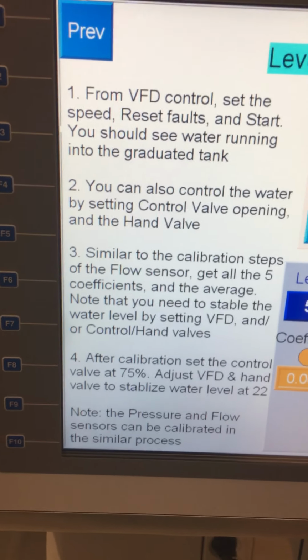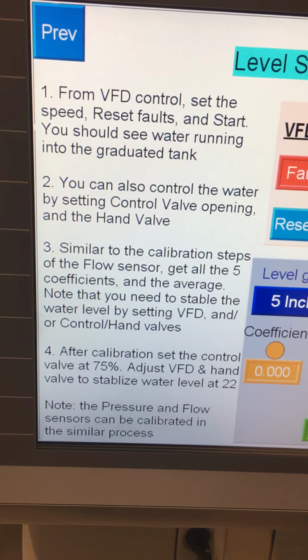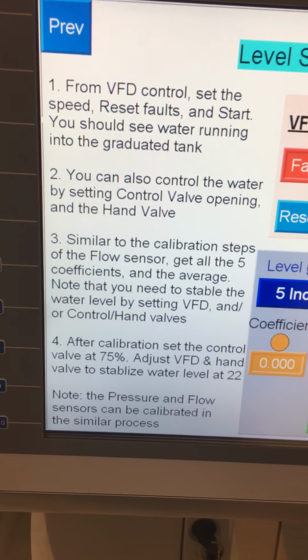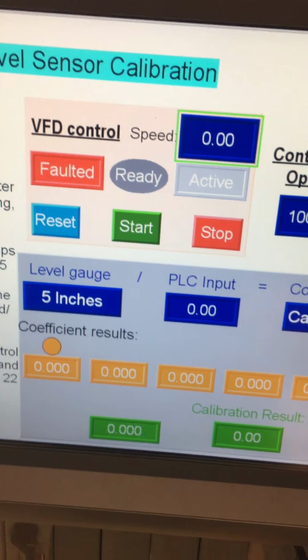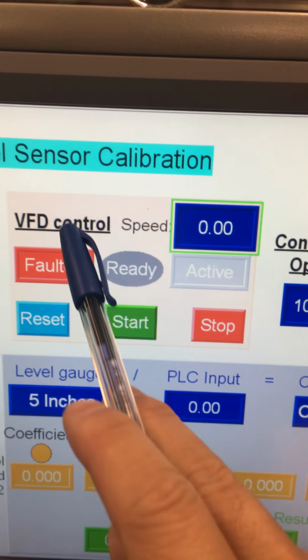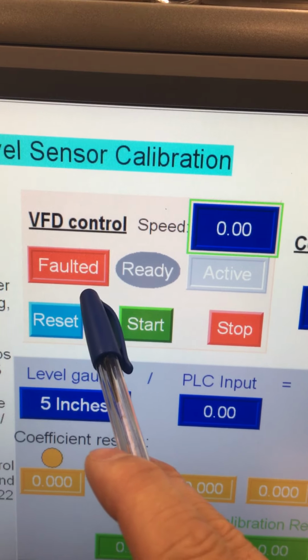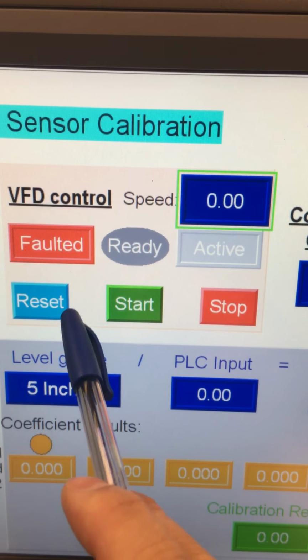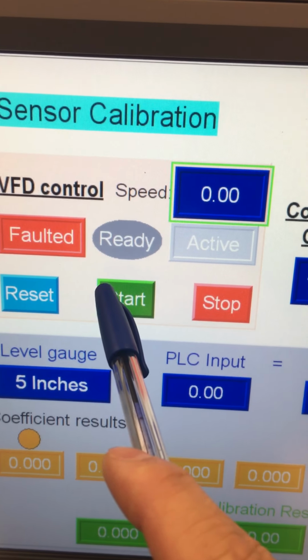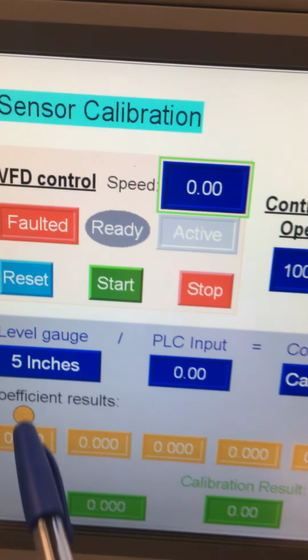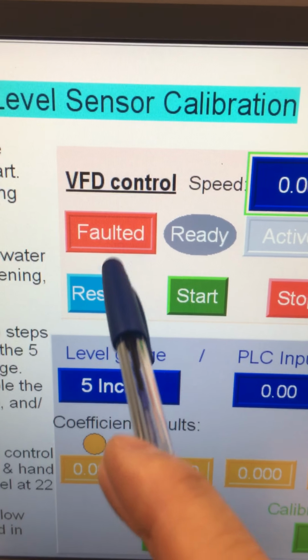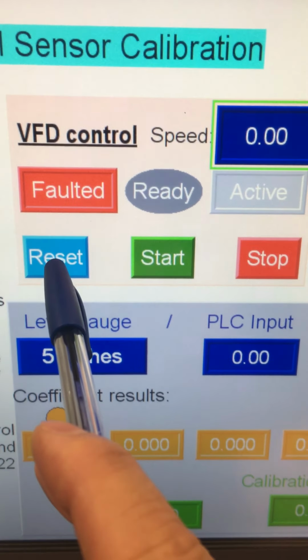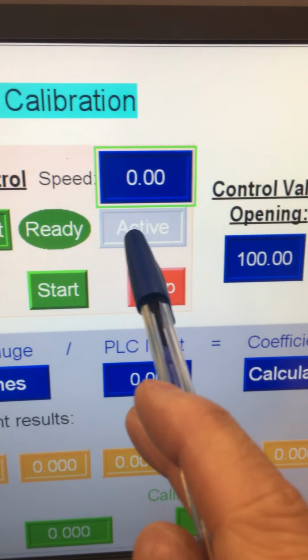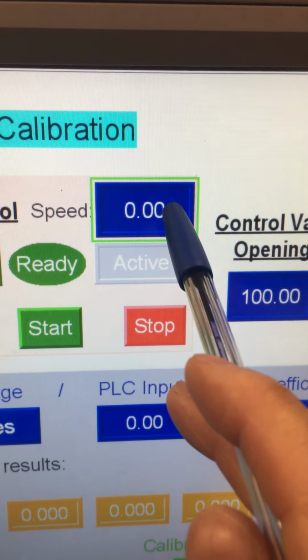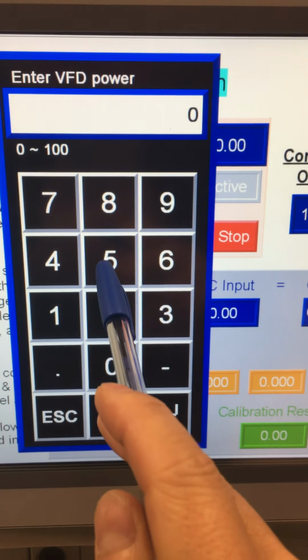And here are those instructions. From the VFD, you set the speed, reset the fault, and start. You should see the water running into the column. Right now you can see this part is the VFD control. It has a fault, so you have to press reset. That depends: if you run it for the first time, you will see the fault. If somebody else already ran it, you probably won't see it. But whenever you see the fault, you can press reset to clear it.